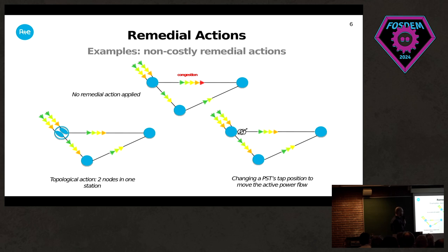Another type of remedial action is the phase shift transformer. Let's say we equip the line with a phase shift transformer. This kind of equipment is able to shift the phase of the current on the line and act on the active power flow, relieving the congestion on the line.